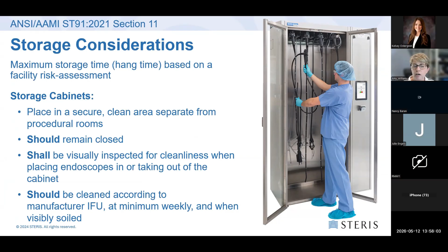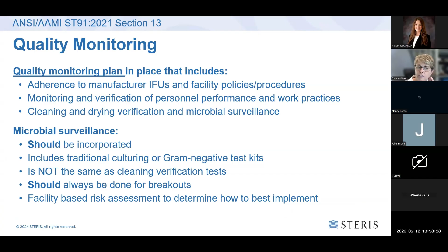Quality management. This is really around microbial surveillance, which right now is not a requirement, but it is strongly recommended that you do some sort of culturing on a percentage of your devices periodically, just to ensure that your cleaning processes are effective. Preventive maintenance, you should have a policy for this. It's not new. We've always done preventive maintenance, but you actually should have a preventive maintenance policy that outlines what is done with devices when damage is identified.